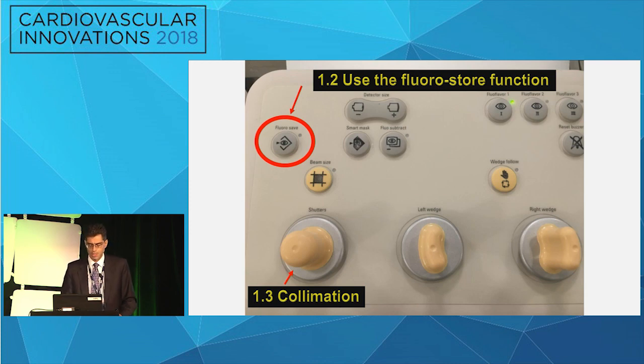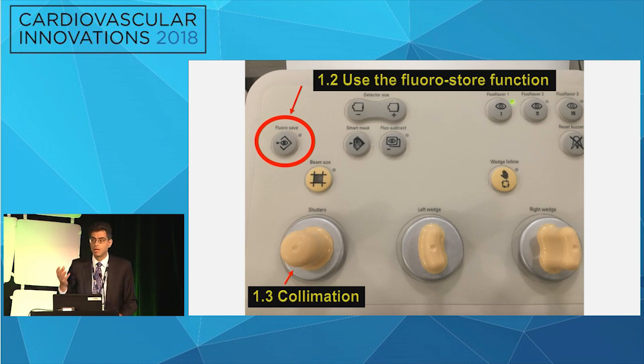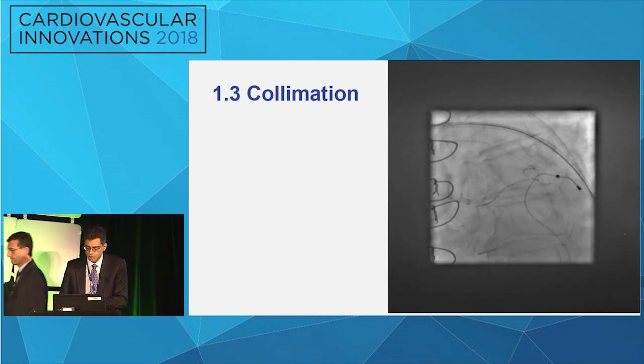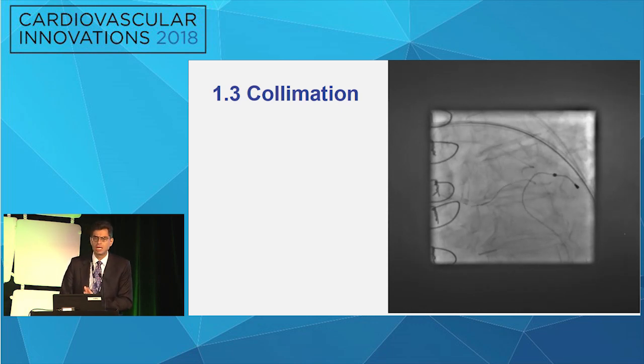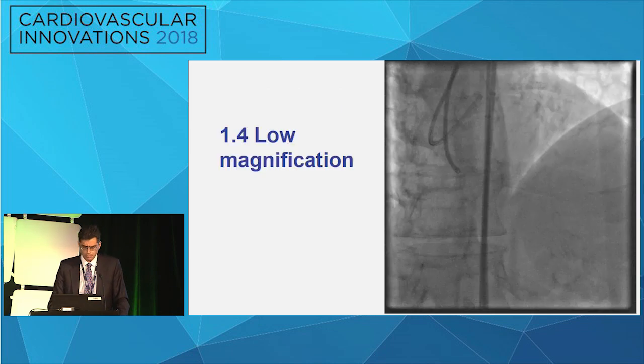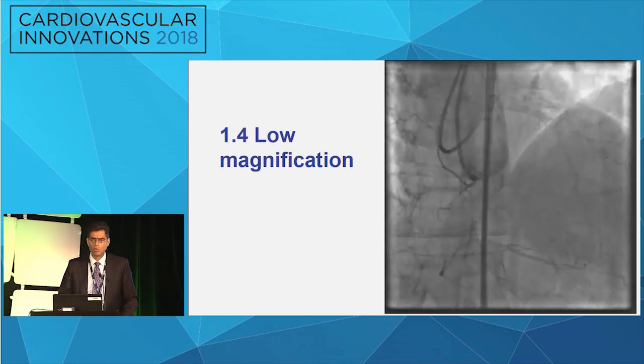There's a button you should know and use routinely several times in a case — the fluorostore button. You do a wire manipulation, save it, fluorostore button — a tenth of the radiation, one second is all you need. Collimation is also not done very commonly. You don't need to see everything — you need to see some things. If your wire tip is outside the field of view, make sure you pan from time to time so it doesn't cause a perforation. Low magnification — with big giant screens, you don't need to zoom in because the electronics do the zoom in for you.